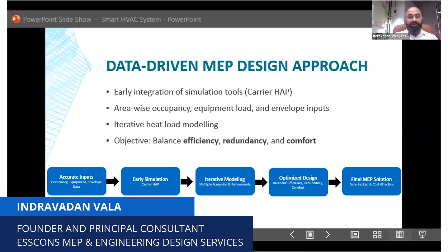So we are providing air conditioning to the machine envelope itself as well as the building, the room itself. How did we achieve that? With iterative heat load modeling - repetitive heat load simulation instead of just a single run, following the modeling process repetitively with different testing conditions, different combinations of occupancy, different fresh air requirements, different time zones.